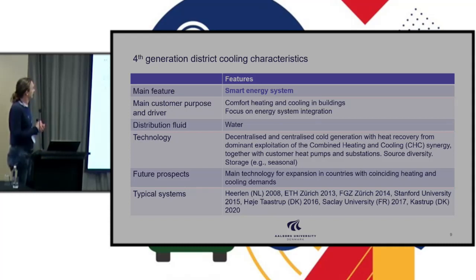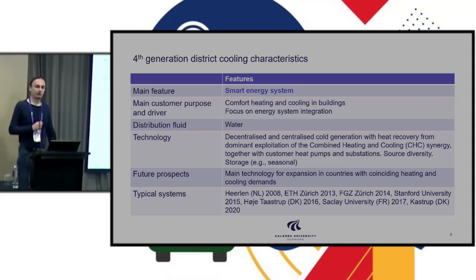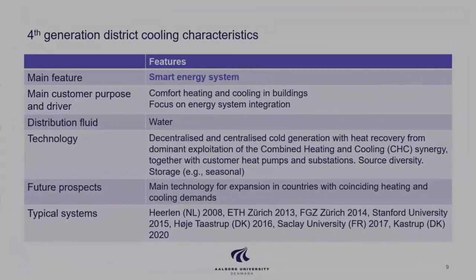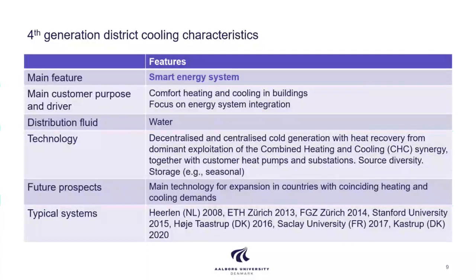Moving to fourth generation district cooling: here we are much more focused on integration with the rest of the energy system. There is a much stronger connection to district heating. When you have a chiller, you will also be producing heat, and if you are in a normally cold country you will have a potential use for that heat. There are Dutch systems, Swiss systems, Stanford, and Danish systems where, typically in colder climates, you can actually make use of the heating you will also be producing.